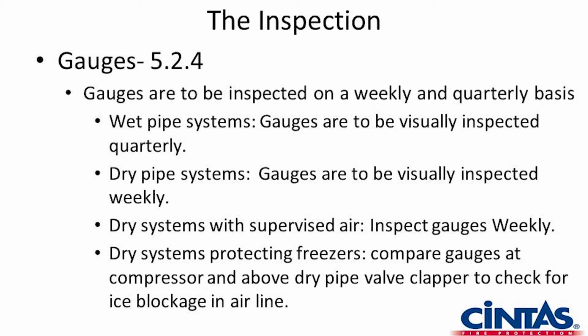Same on dry. Gauges are to be inspected weekly there. Dry systems with supervised air inspected weekly. Dry systems protecting freezers, compare gauges at the compressor and above the dry pipe valve of the clapper to check for ice blockage in the airline.